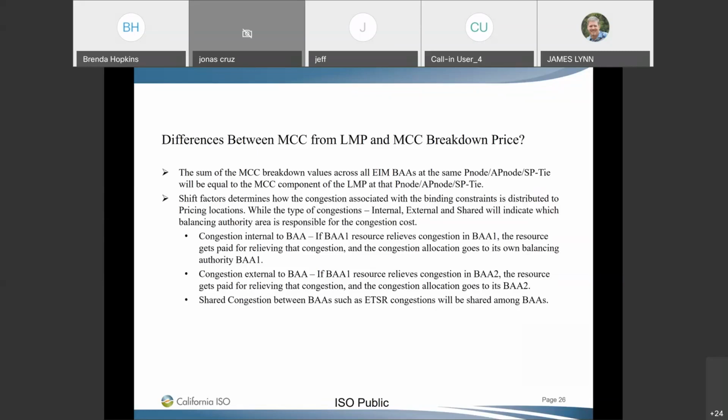But for the most part, when you have a separation, you are resolving internal congestion because your generation is moving to meet your load. Therefore, when you first get the pricing, it used to be that you would have some unusual marginal cost congestion, and we have to go in and fix it. We do a price correction based upon that. But with the market settlement timeline, that market price correction should be performed before we even do a statement. So what you will see is all the congestion for that internal generation should meet the congestion for your demand.